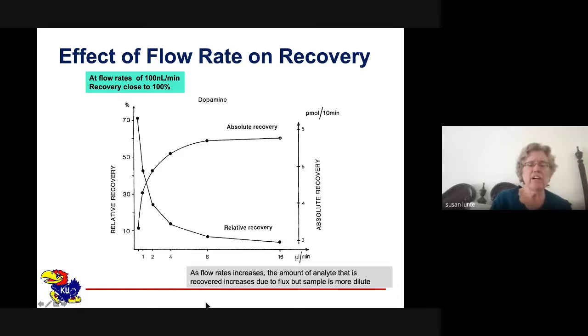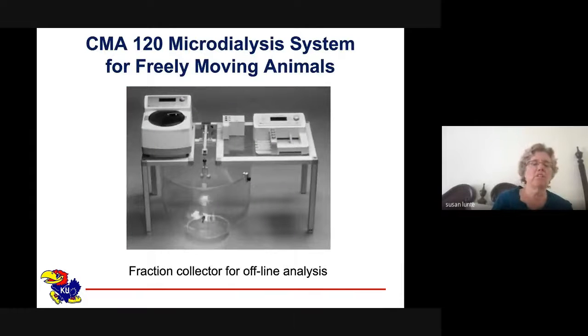Now, if you increase the flow rate, you decrease the recovery, but you do actually get more mass into the sample, even though it's a more dilute sample. But typical flow rates that are used are usually around 1 microliter per minute, 1 to 2 microliters per minute. So a typical commercial microdialysis system usually consists of a bowl where you can have the rat running around, the microdialysis syringe pump for the microdialysis perfusate, and then a fraction collector to collect the samples offline.